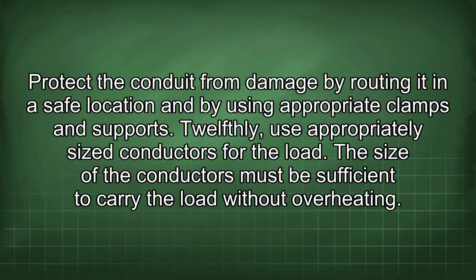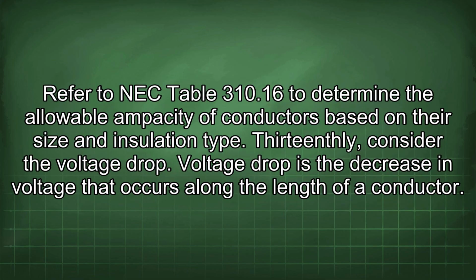Twelfthly, use appropriately sized conductors for the load. The size of the conductors must be sufficient to carry the load without overheating. Refer to NEC Table 310.16 to determine the allowable ampacity of conductors based on their size and insulation type.